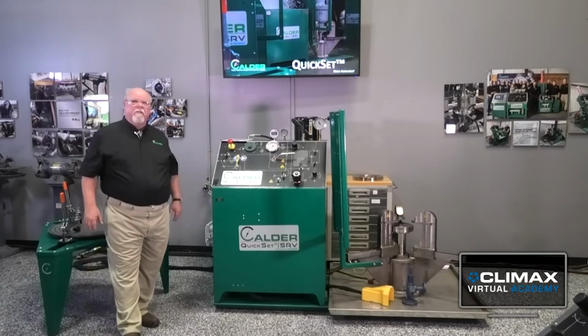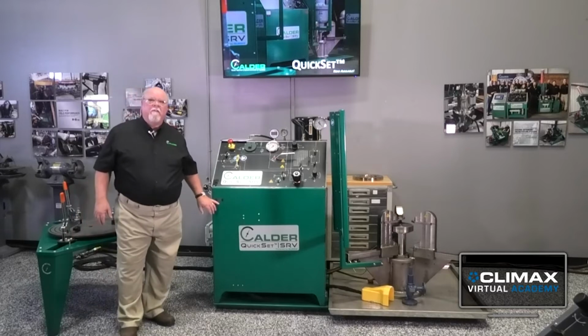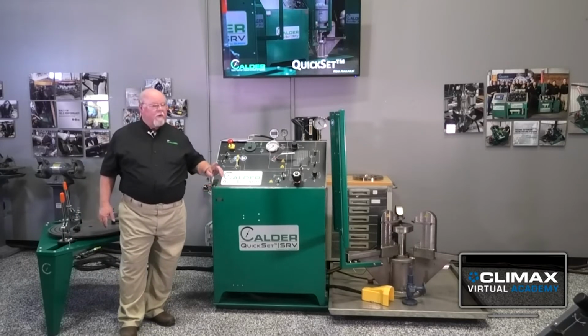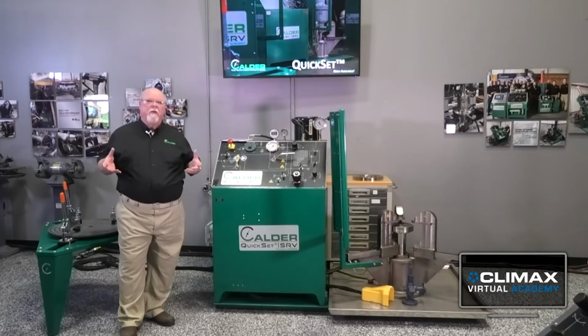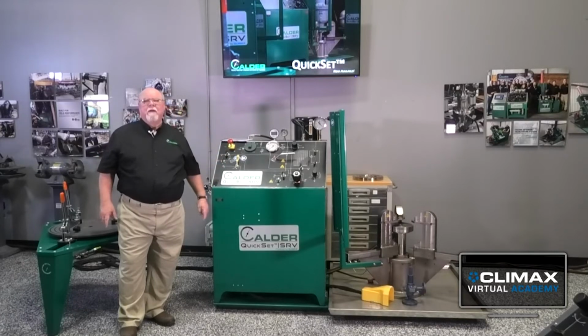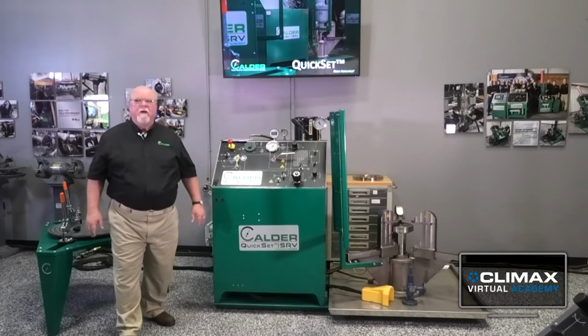This machine is an industry first. It's standard field upgradable clamp force options from 30 to 60 tons. And where that comes into play is how much clamping force is needed to hold the valve to the test port as you put the test pressure to it. So if the valves are small or low enough pressure class, then the tonnage can be low. But as that pressure or the valve size or the combination of the two get high enough, then 30 tons is no longer going to be adequate to hold those valves down, and then you won't be able to test. So we can go up to 60 ton. It's field adjustable, so it's a tremendous, industry first option as well.